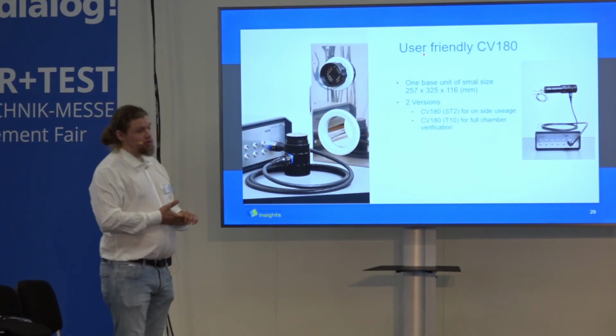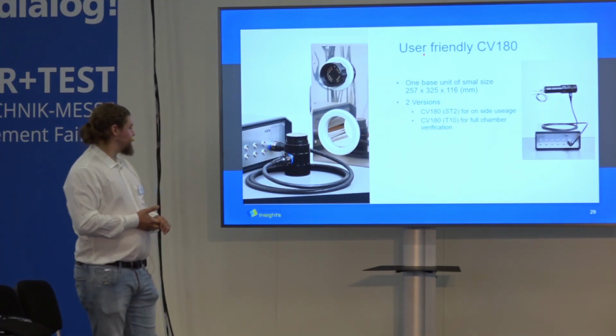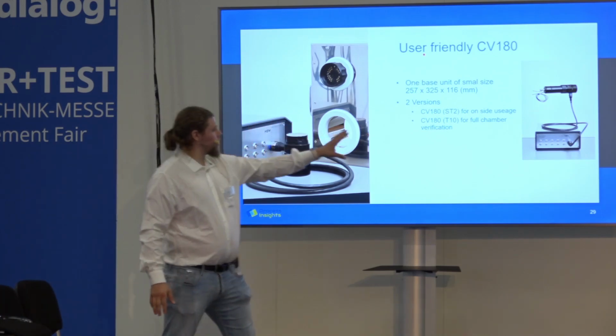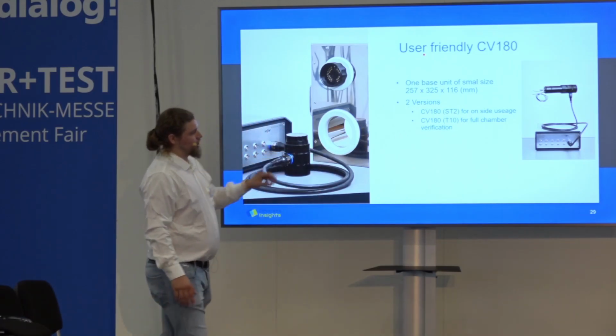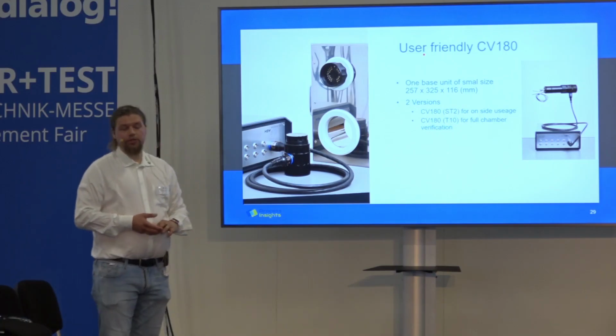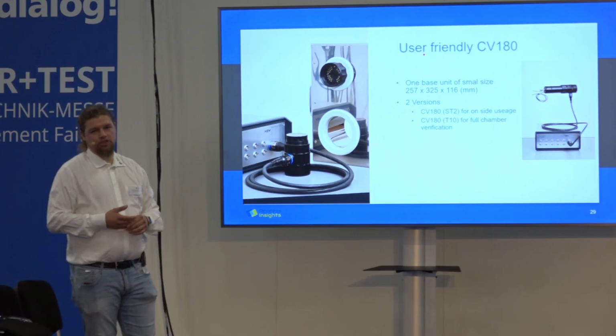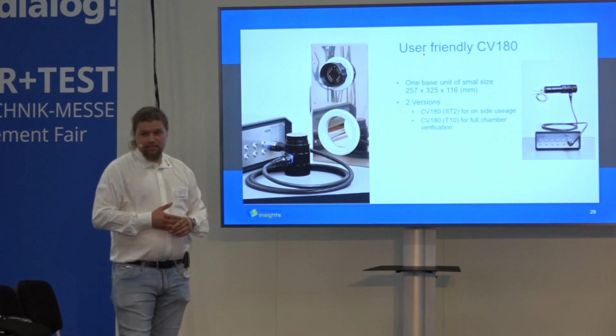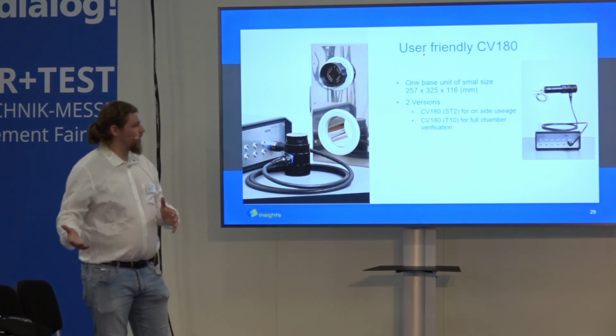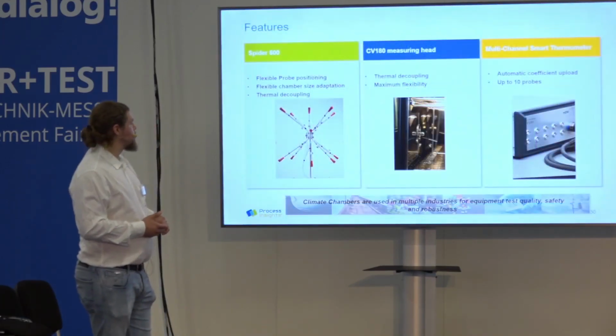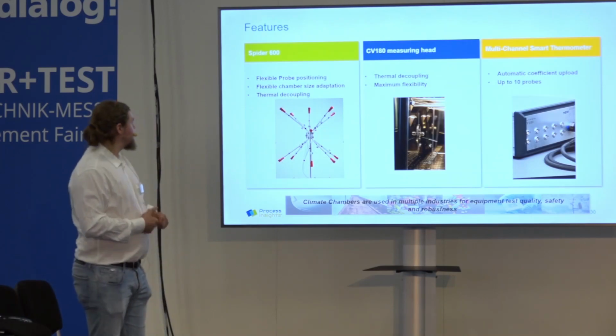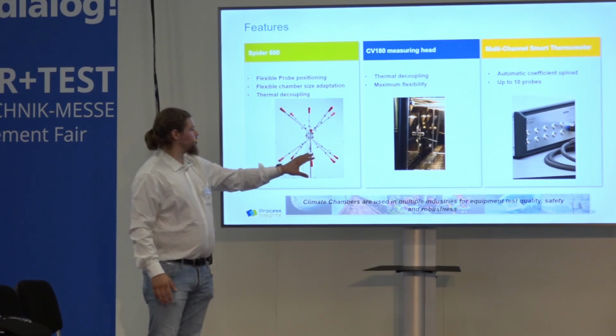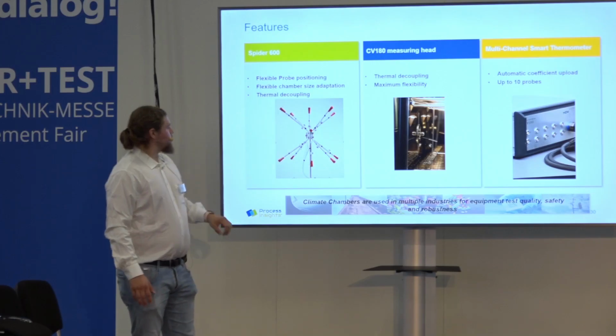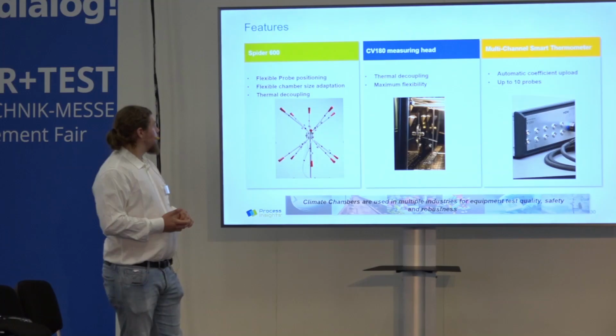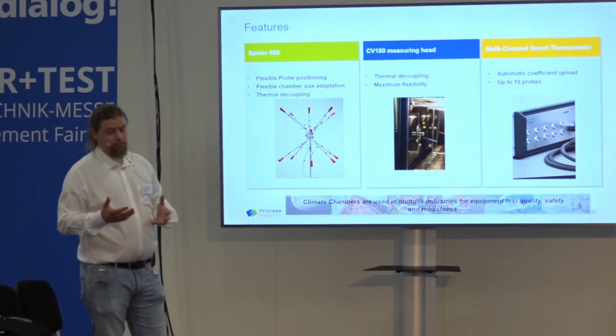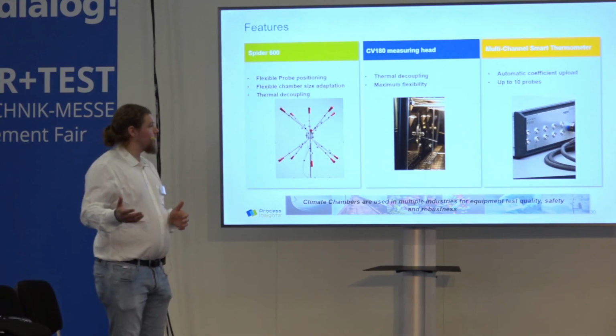So there is a new solution from MBW, called CV180. You can see here that it's only one unit with a measuring head. You can attach up to 10 temperature probes and also the chilled mirror to it. So it's a simplified solution for climate chamber providers. They were urgently asking for such a solution to be able to work faster in their processes and also more reliably. So what opportunities do we now have with the CV180? We need the useful volume represented by the temperature probes, which you can see here, so that we can find a representative value for the temperature, the average temperature value, which is provided by the chamber control.